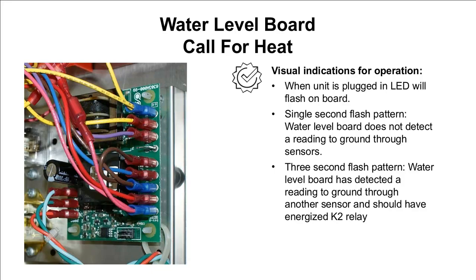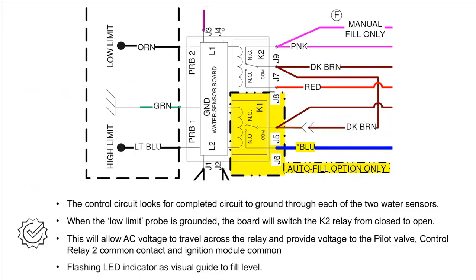Now, how does it do that? This is a close-up of our water board. Here, you can see the control circuit. There's our incoming power, and here are our 2 water sensors. The control board is mainly looking for a signal through our low water sensor to ground. When it receives that signal, it will close this relay right here. We have the dark brown power, which is flowing from our control board. When the relay closes, it is supplied to this red wire.